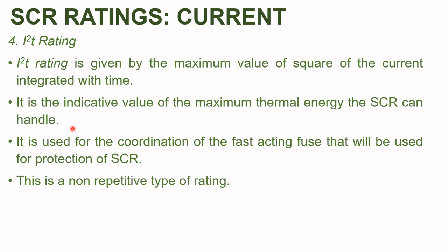It is used for the coordination of the fast acting fuse that will be used for the protection of SCR. This is a non-repetitive type of rating. Once this rating is exceeded, the SCR will get damaged.